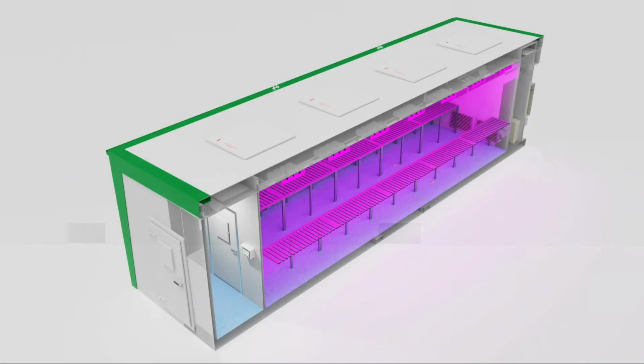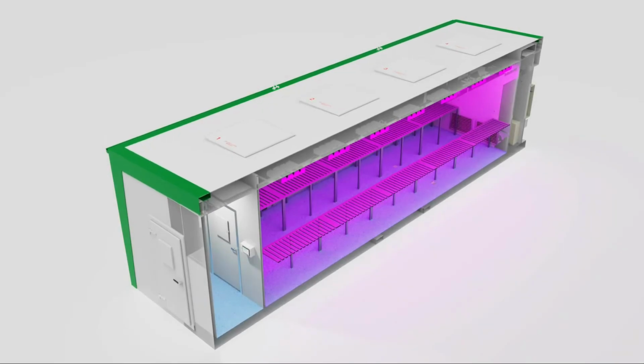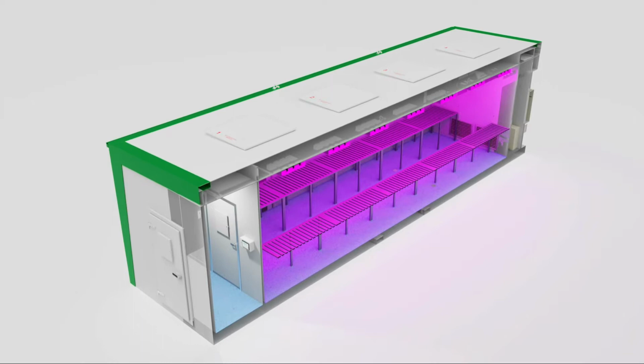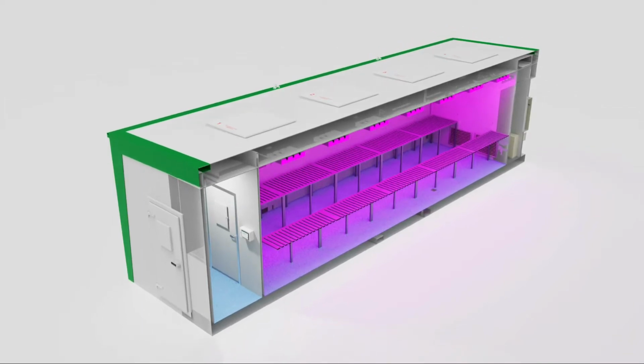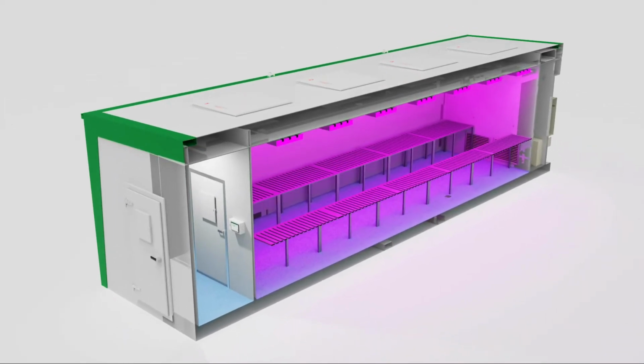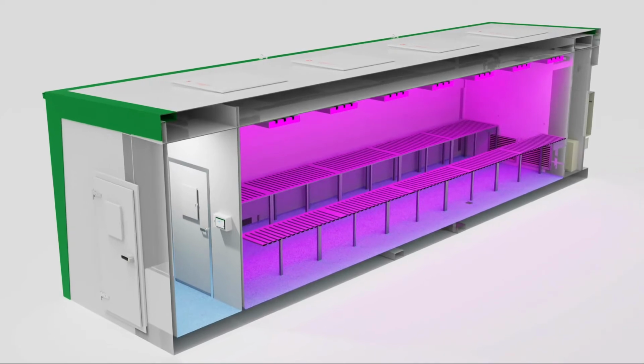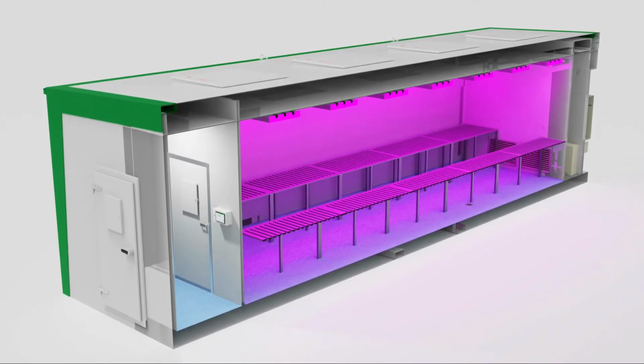The chamber is easily lifted into position using either forklift slots or lifting lugs at the top of the chamber. As a self-supporting structure, the chamber can be deployed almost anywhere that has access to power and water. For remote areas, battery or diesel operated modules can be connected.